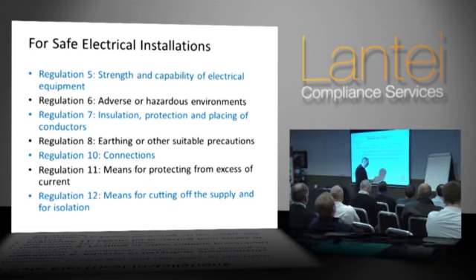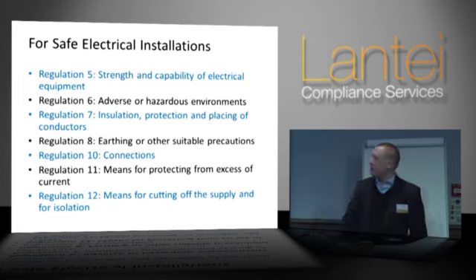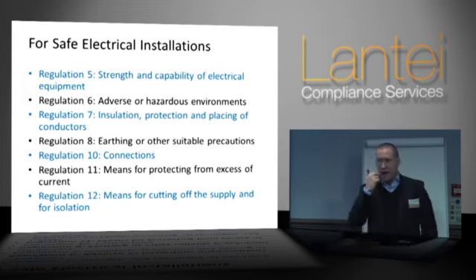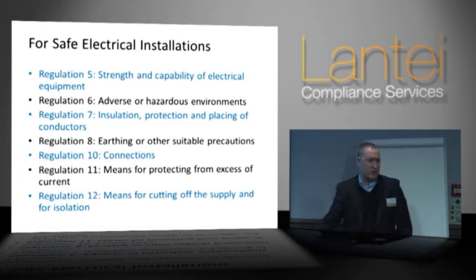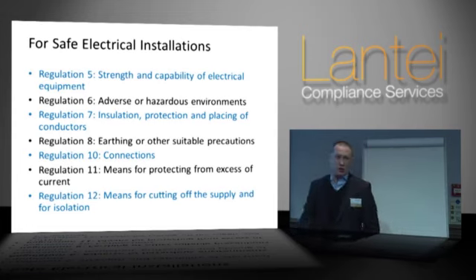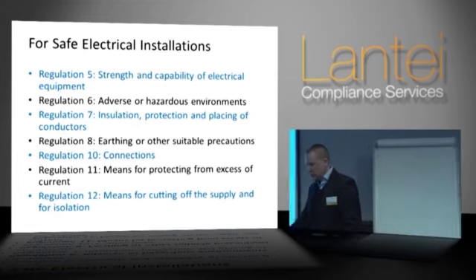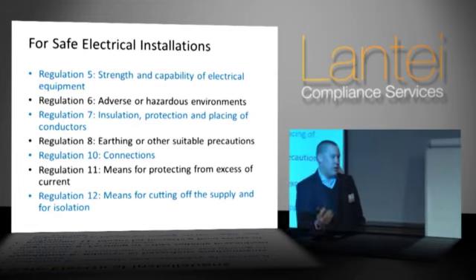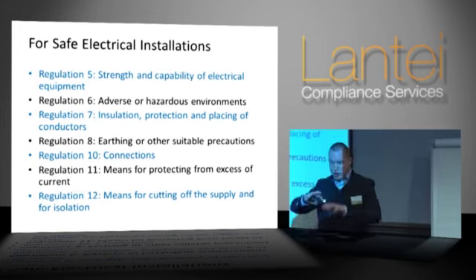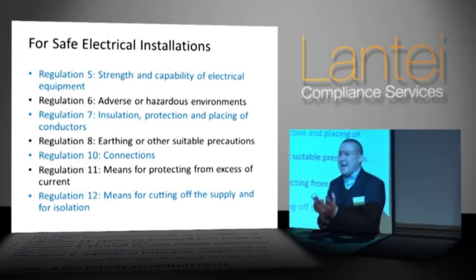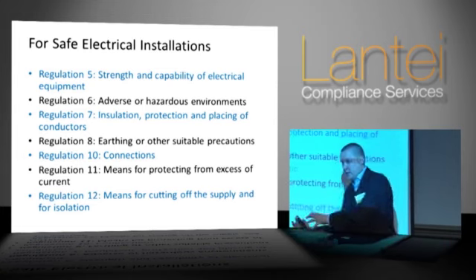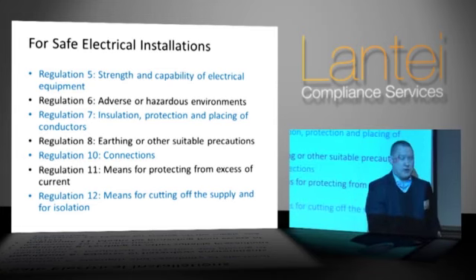Your next one, Reg 6, talks about adverse or hazardous environments. There's two aspects to this. First, hazardous environments, potentially explosive atmospheres, where we've got combustible liquids, gases or dusts. Regulation 6 wants us to identify any electrical equipment that can create a spark, and then enclose that equipment - this is where we get EX-type equipment from, that prevents the spark igniting the outside atmosphere.